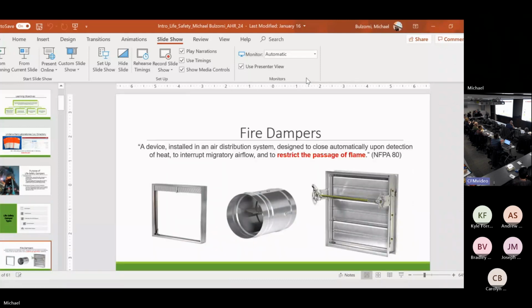So what's a fire damper? There's your definition from NFPA. We care about one thing with a fire damper. It's in there in red. We want to restrict the passage of flame. This is a fire rated wall. This partition is continuous. As soon as I penetrate it for an HVAC duct, I need to make up that hole. There's now a protection gap in that hole. So the rating has a fire resistance rating on the wall. I take a damper with a fire protection rating. I put it in there.